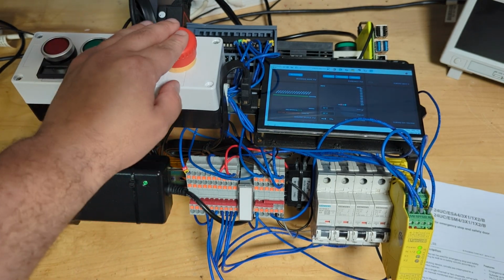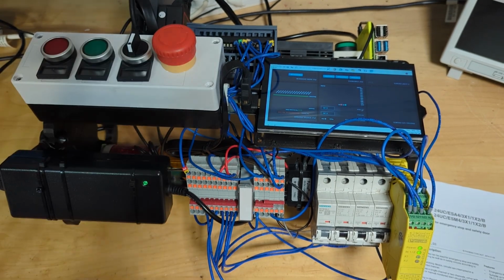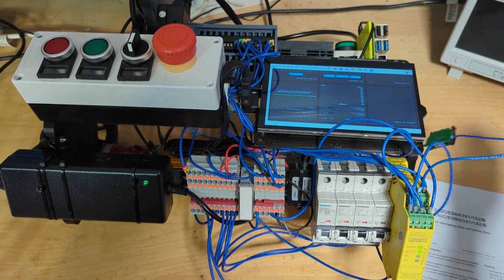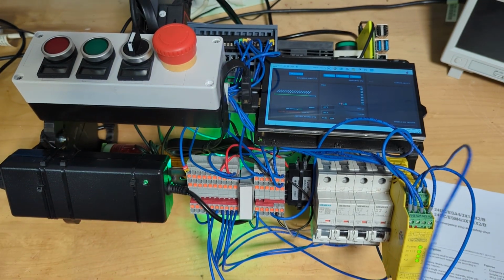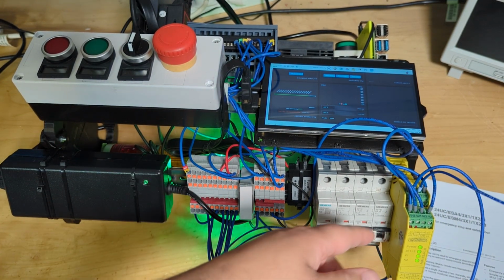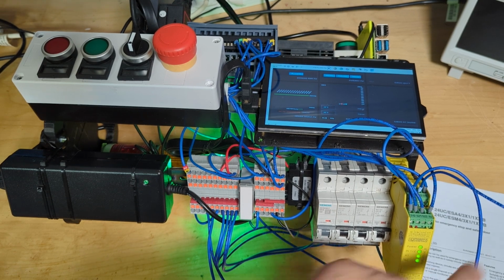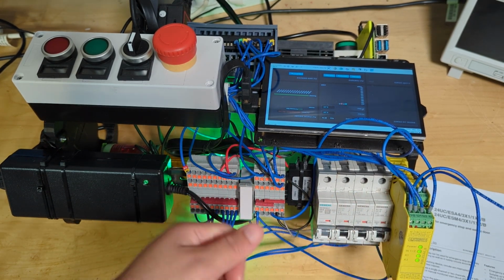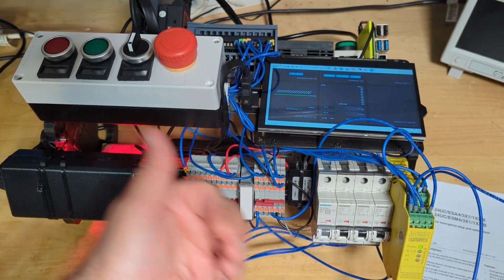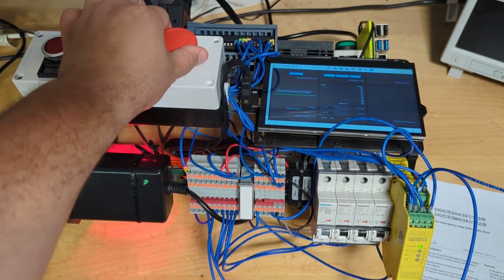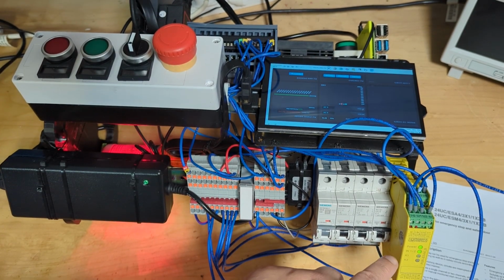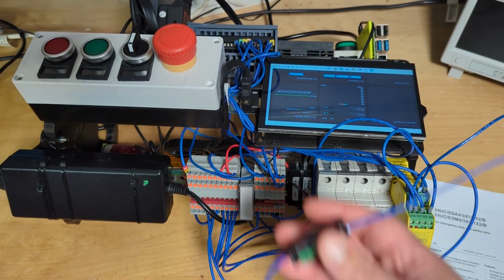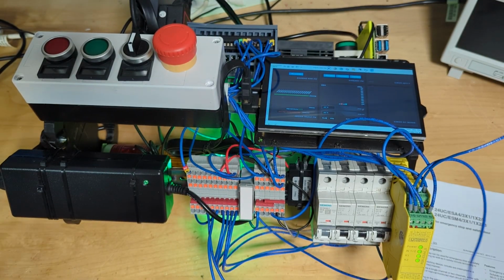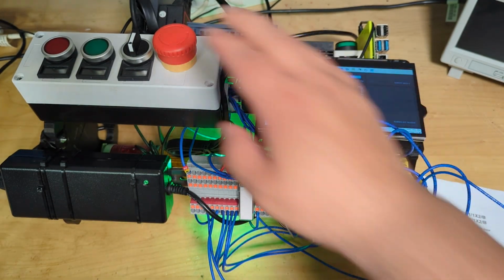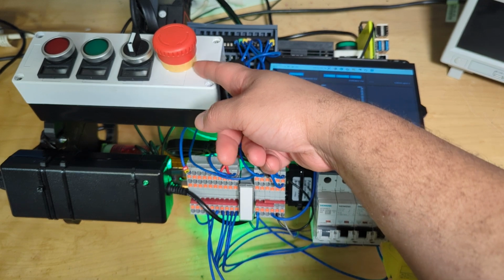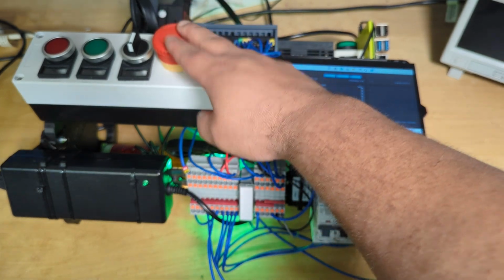So the status of my e-stop goes into my safety relay and my safety PLC. So depending on the state of it, you can see that I've got four LEDs. This safety relay is happy. I hit the e-stop, I've only got one, it's unhappy. If I reset it, I've got two LEDs, so it's ready, but until I press this, it's not actually. So first misconception is that you're not cutting power when you hit that e-stop, so don't think that you are.